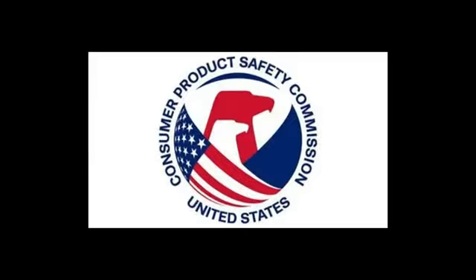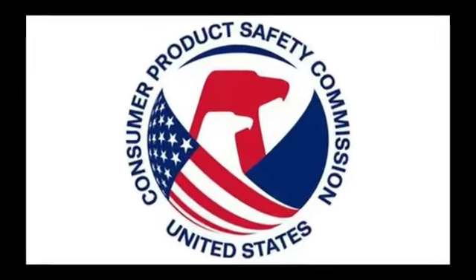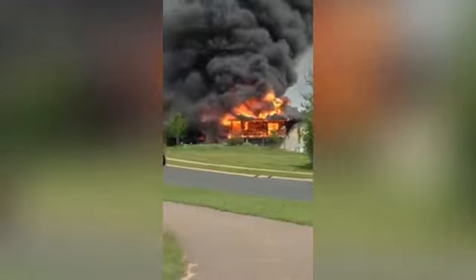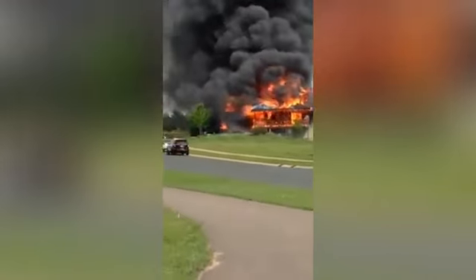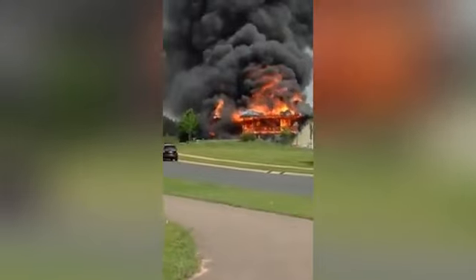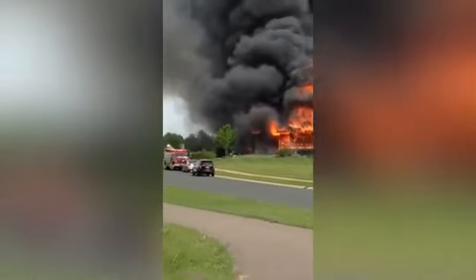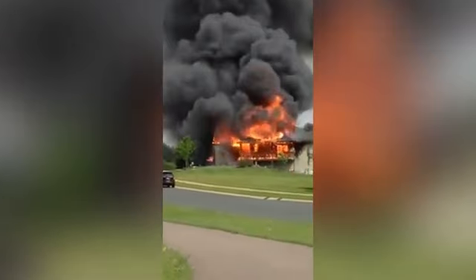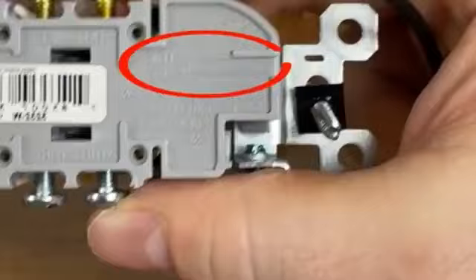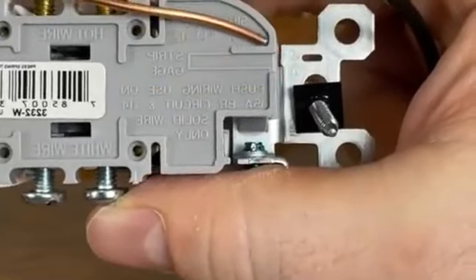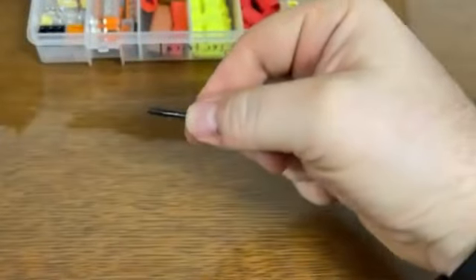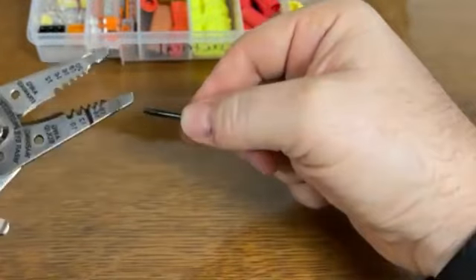The Consumer Product Safety Commission studied homes wired with aluminum. They found these homes are 55 times more likely to reach fire hazard conditions at connections than homes wired with copper. 55 times. Builders installed aluminum branch circuits in roughly 2 million American homes. Most owners do not know.